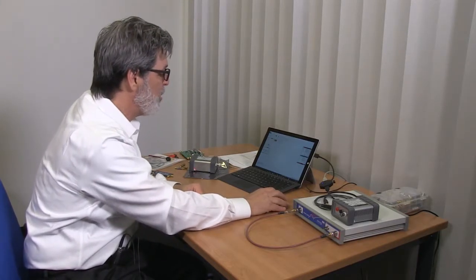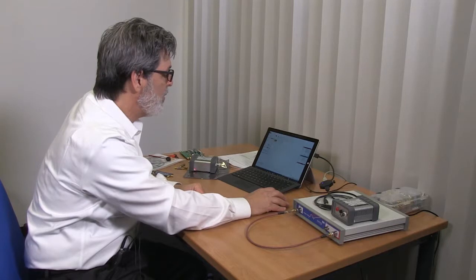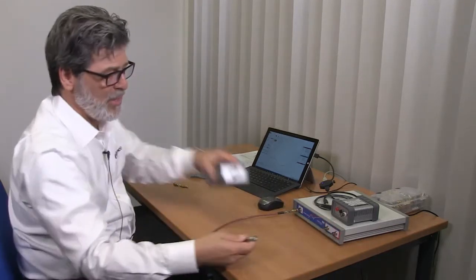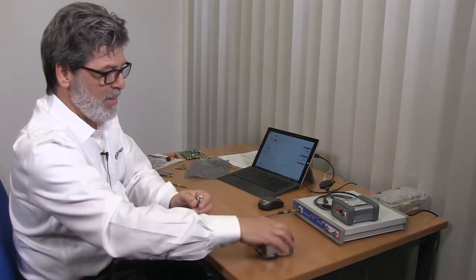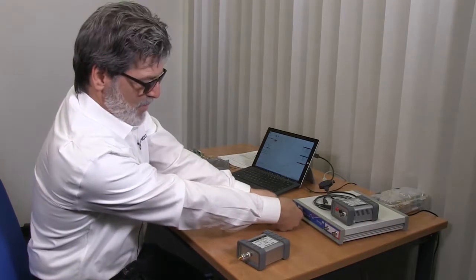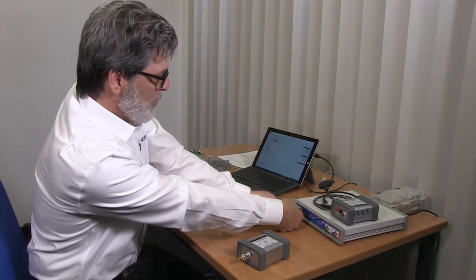When we make low impedance measurements, it's important that we include our common mode coaxial transformer because that is the part that cancels that low resistance for us.